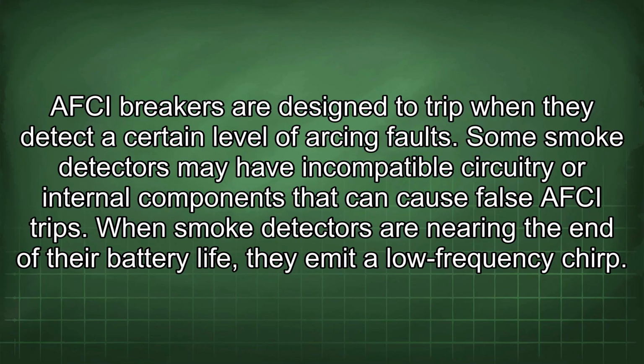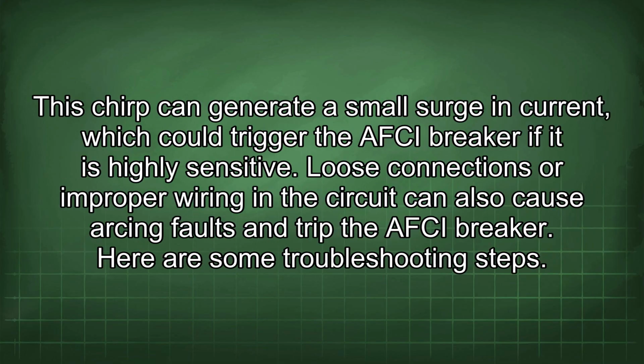AFCI breakers are designed to trip when they detect a certain level of arcing faults. Some smoke detectors may have incompatible circuitry or internal components that can cause false AFCI trips. When smoke detectors are nearing the end of their battery life, they emit a low-frequency chirp. This chirp can generate a small surge in current, which could trigger the AFCI breaker if it is highly sensitive. Loose connections or improper wiring in the circuit can also cause arcing faults and trip the AFCI breaker.